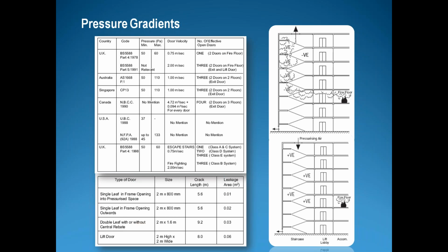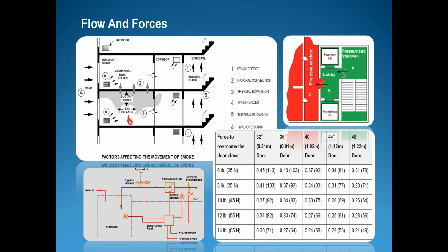Remember the pressure gradients. It means that we have to be sure that the pressure gradients inside the elevator shafts and the stairs, the egress stairs or escape stairs, will not exceed a certain level. Otherwise, old people and young children cannot open the door because of the pressure on the other side. So we have a table from the British standard that states the size of the door and the force required for the door closer. And here, how can I control the pressurization fan? And sometimes we use an airlock, a vestibule between the egress stairs and the affected area.